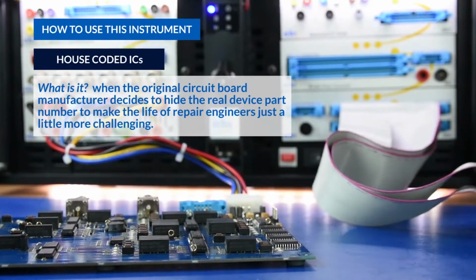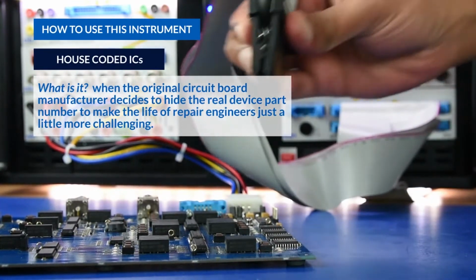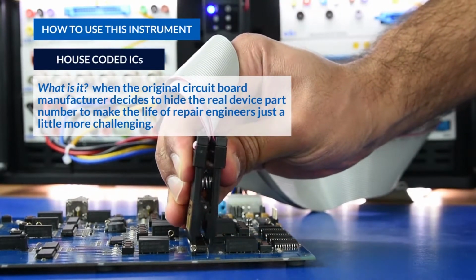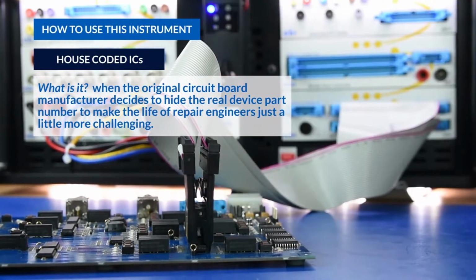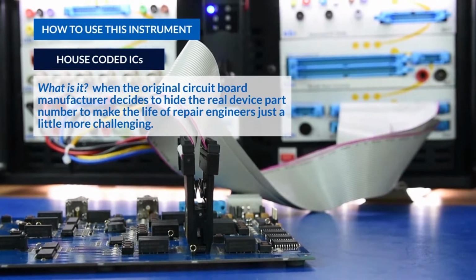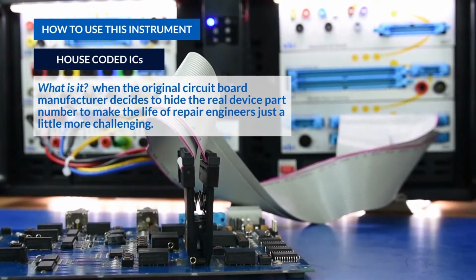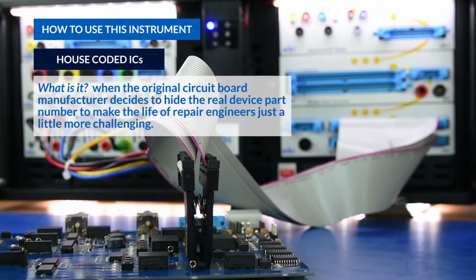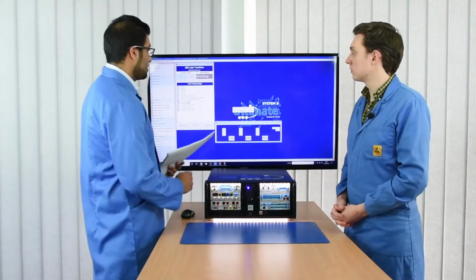When you get an IC and you don't know what it does, it's just been house coded, such as ABB or Siemens, you can actually use this to click on there and see how that IC functions and maybe see what the original IC was. Great. So that was the first part of episode 5.